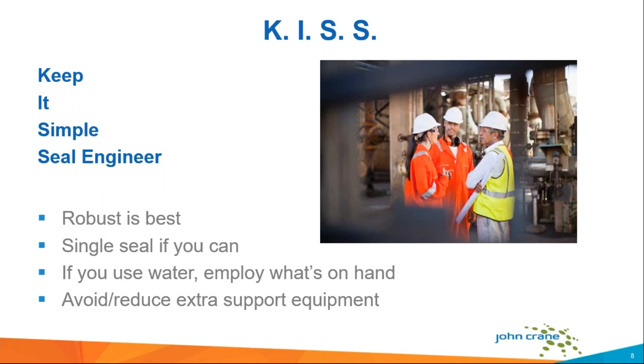We looked at a few different design options, including pressurized dual seals, but decided to avoid as many bells and whistles and support equipment as possible — the KISS principle: keep it simple. The seals worked even better than hoped for and ran for years on end without need for replacement. This was a Goldilocks story: we got rid of a lot of water, didn't push the seal limits too far, and everything worked just right.